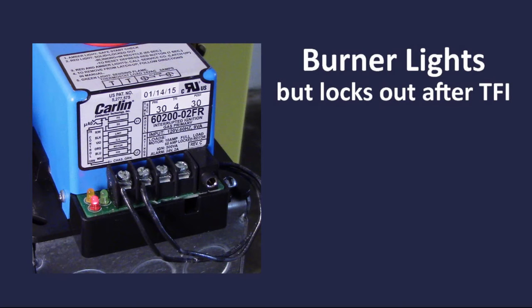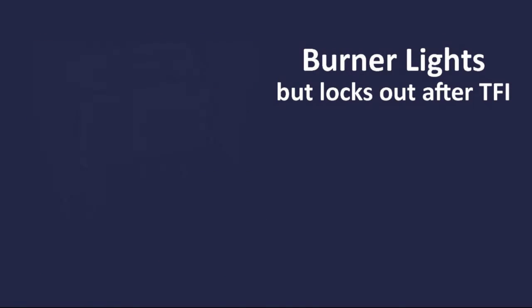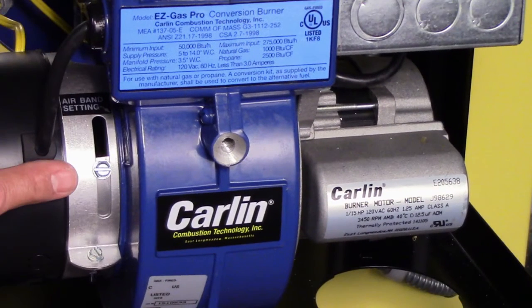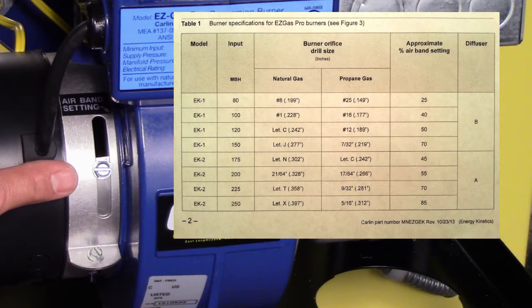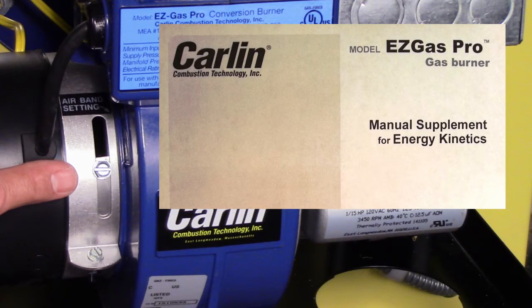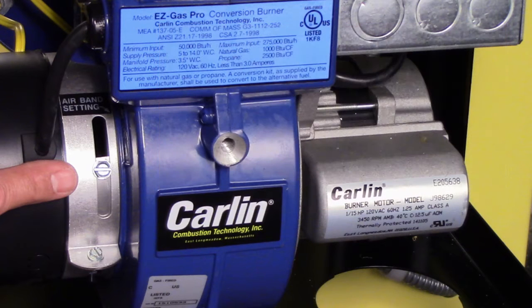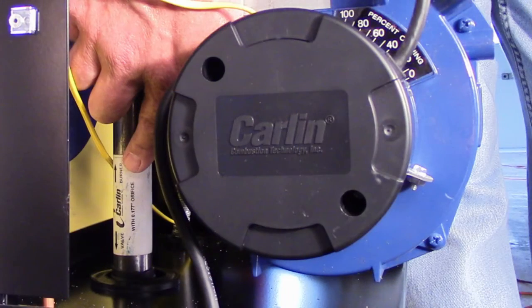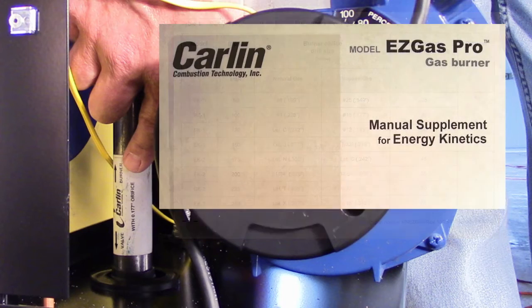If the burner lights but locks out after trial for ignition, begin troubleshooting this condition in much the same way as if the burner wouldn't light. Check the airband setting against the gas burner settings table found in the EZGas Pro Manual Supplement for Energy Kinetics. The final air settings will be determined by performing a combustion test with the airbox cover installed. Also check the orifice size against the gas burner settings table found in the EZGas Pro Manual Supplement for Energy Kinetics.